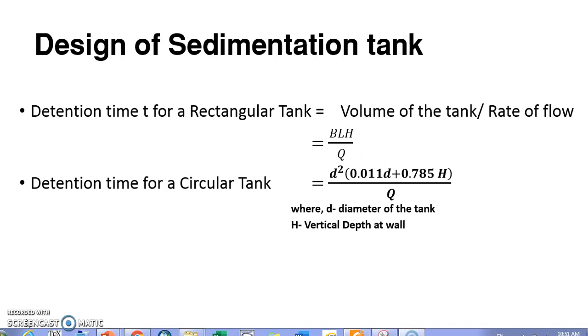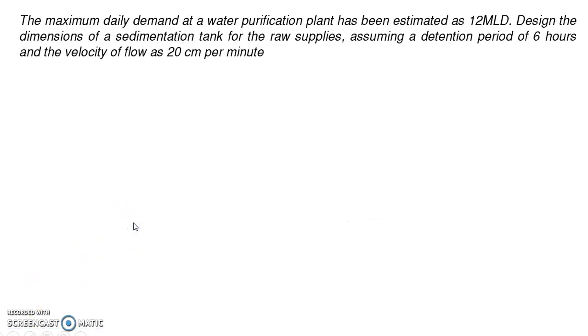When it comes to the circular tank, the retention time can be calculated as D² × (0.011D + 0.785H) whole divided by the rate of flow (discharge), where D is the diameter of the tank and H is the vertical depth at the wall.